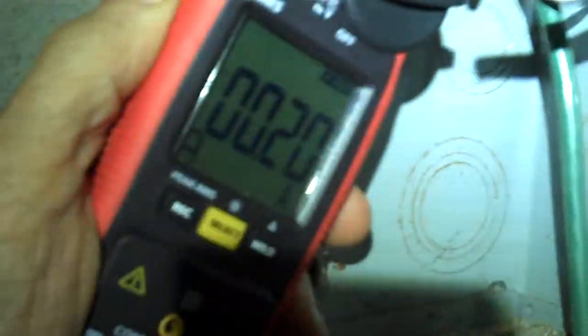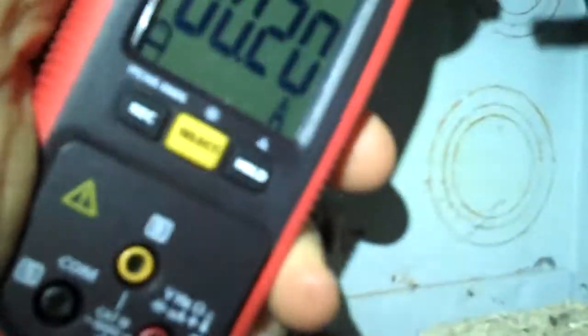So what I'm going to do is reset it, and I'm going to set up for another one. This one I'm going to set up now for the other phase of power, which you will measure right there. And I'm going to set this up also for the peak RMS measurement. And I just want to get the clamp on in the small gap. When it's in the small gap, that's the way to get a more accurate measurement of current. So I'm just going to try to position that so the wire falls in the small gap, before we repeat the measurement. It's having a little trouble staying there, but I'm just going to hold it there. That's okay. And I have a little trouble with my lighting because of the position of the camera and my headlamp.